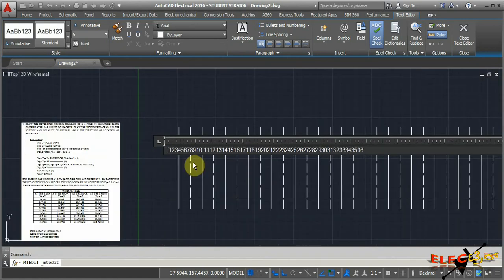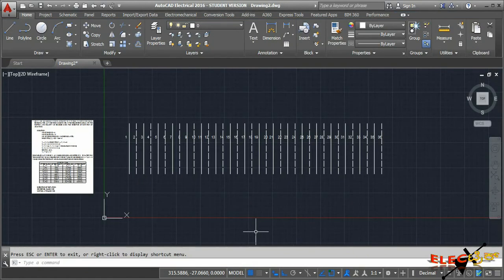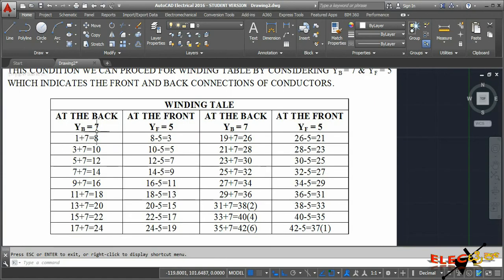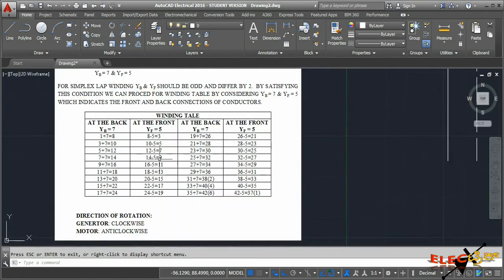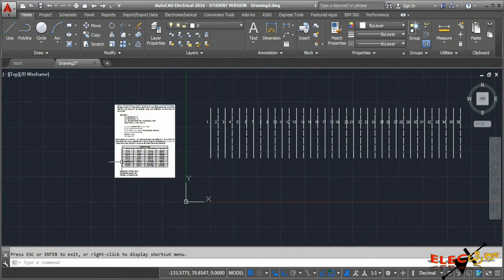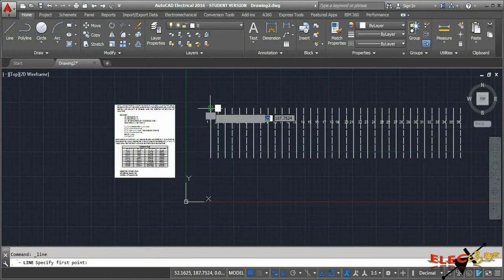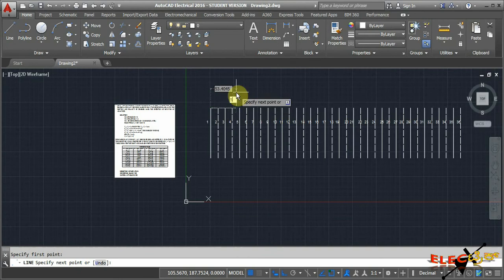After numbering, arrange the numbers for respective conductors - top layer gets odd numbers and bottom layer gets even numbers. Now connect the front and back connections from the winding table. Conductor number one is connected to conductor number eight at the back, and at the front conductor number eight is connected to conductor number three. I'll draw lines at 45-degree angles to show these connections.